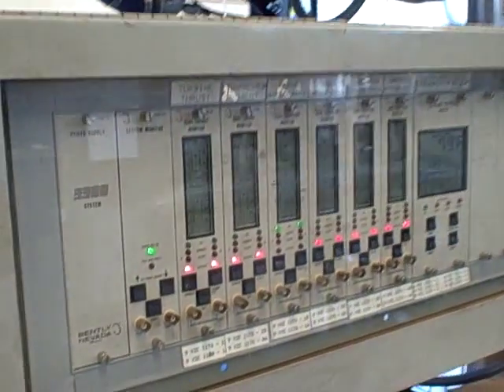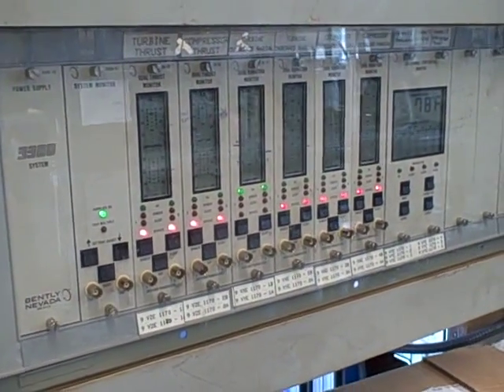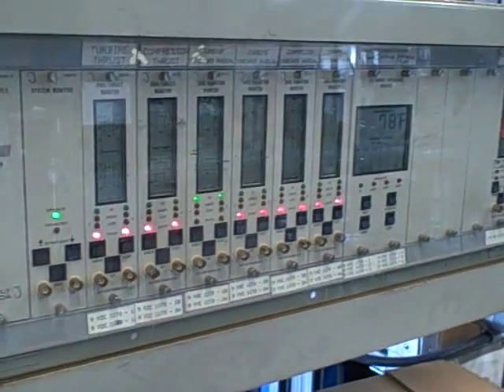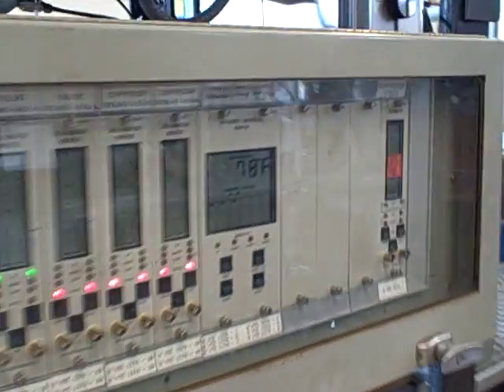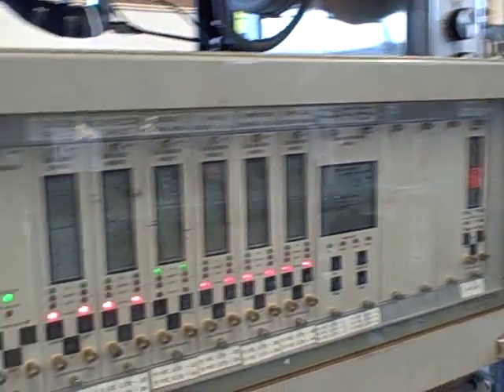Vibration monitoring for the Bently Nevada system is also tied into the shutdown PLC. So if we have excessive vibration on either the oil pump or on the air blower, that will shut the turbo down. Similarly, we have shutdown protection on temperature — if our temperature exceeds the preset limit, we will shut the turbo down.